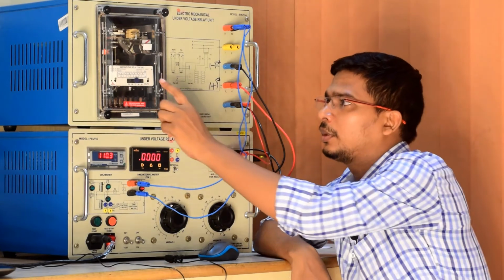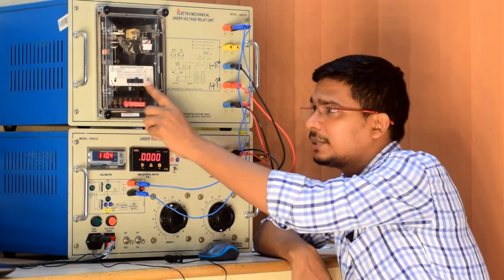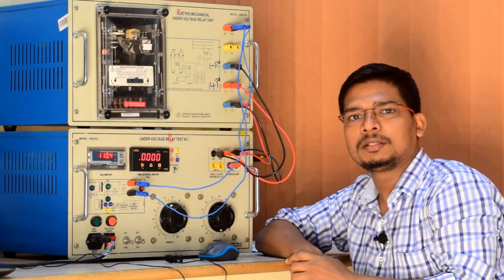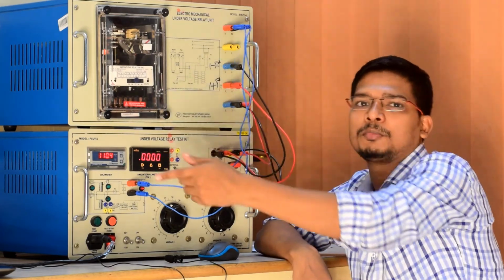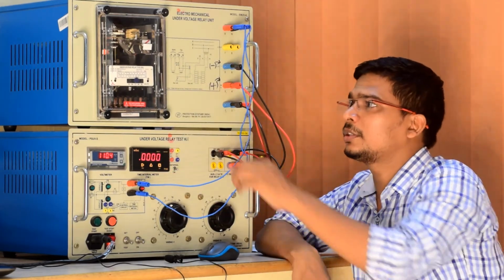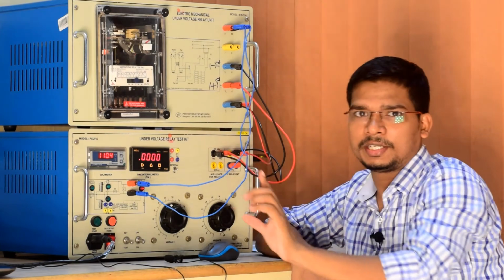But what happens if we change the plug setting from 77 to 99? At that time the relay will come to its trip mode, because 90 is less than 99, that is the plug setting.